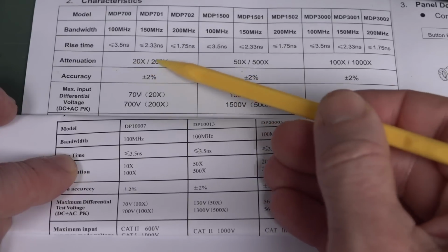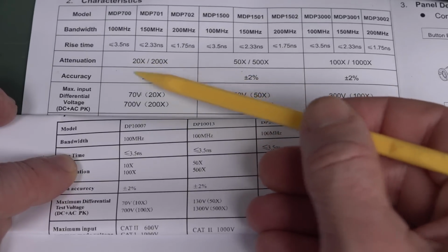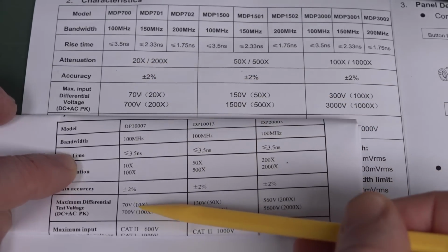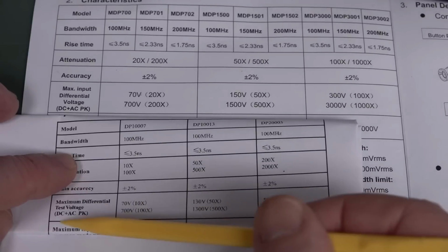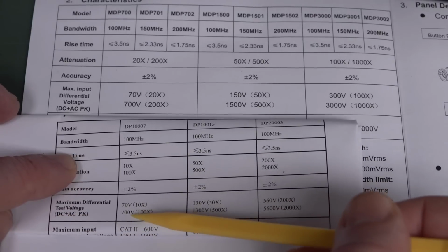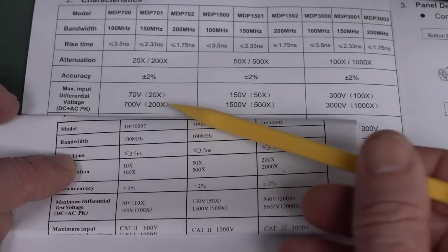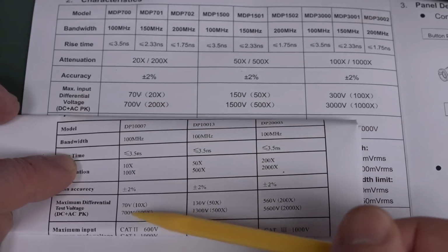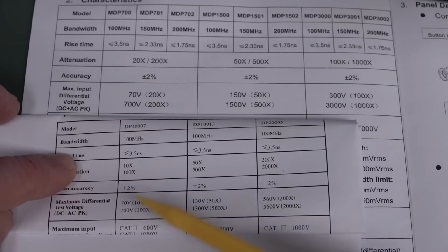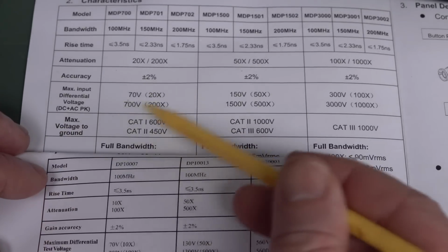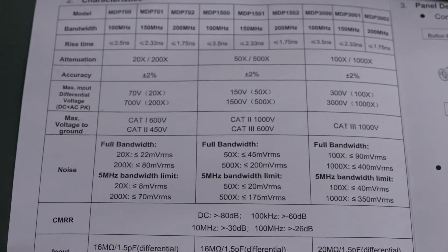But the difference in the attenuation here, times 10 to times 20, hasn't impacted the maximum differential voltage, which is DC plus peak AC — still 700 volts on either the times 200 or the times 100 range with the old model. So it's still more than capable of doing your general purpose mains power supply stuff. No worries whatsoever.